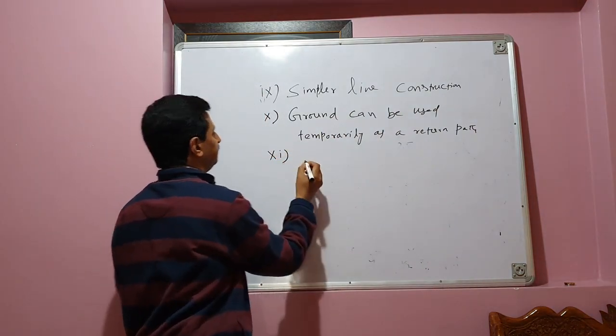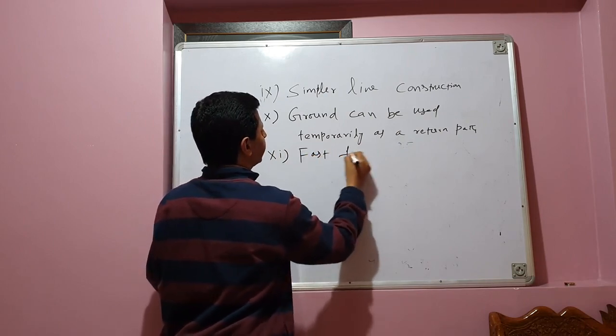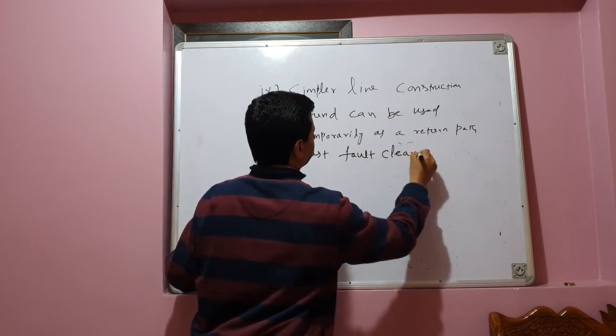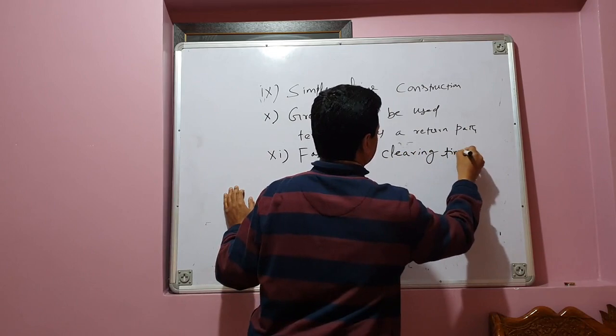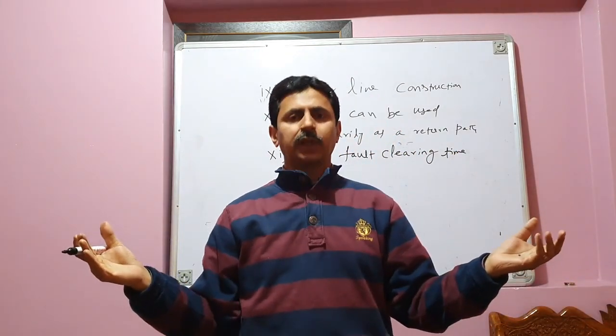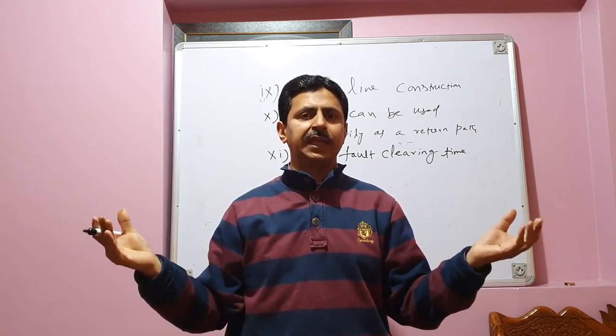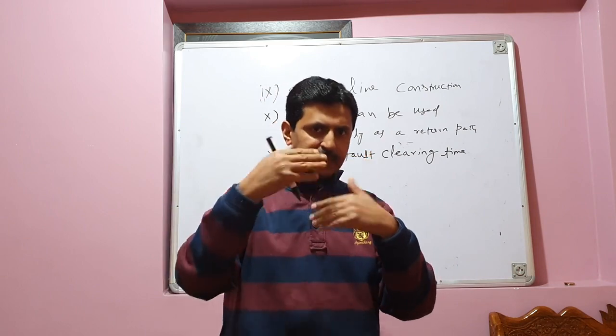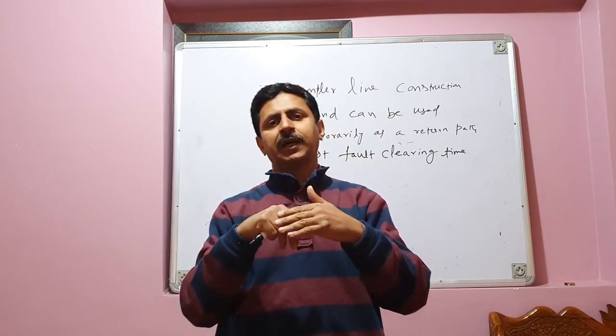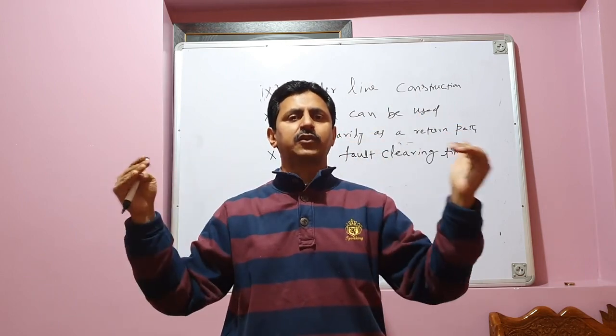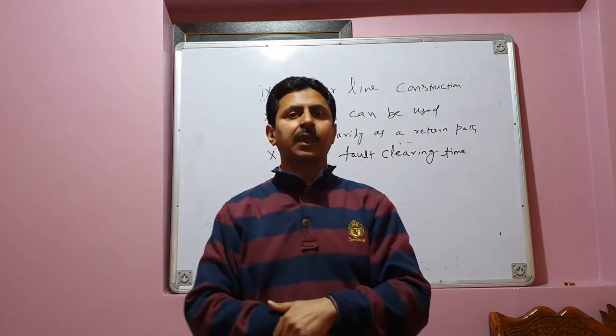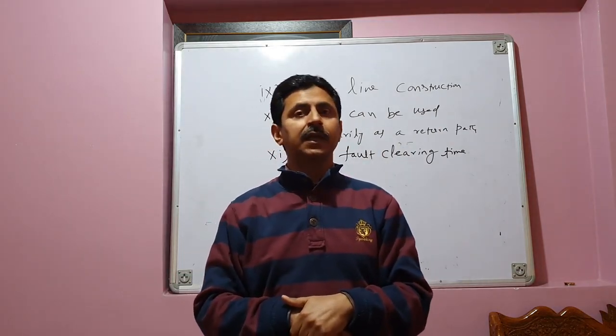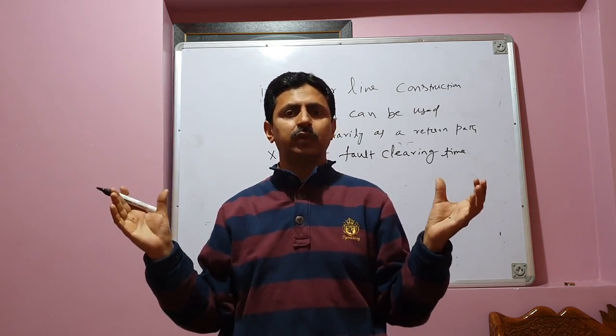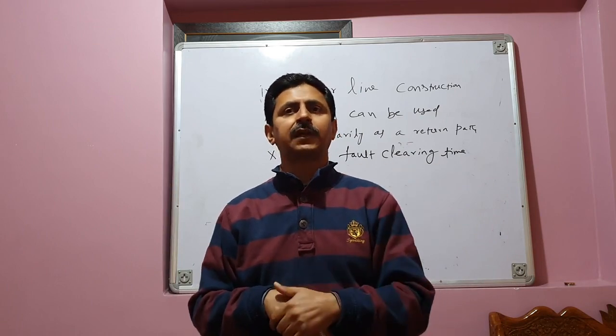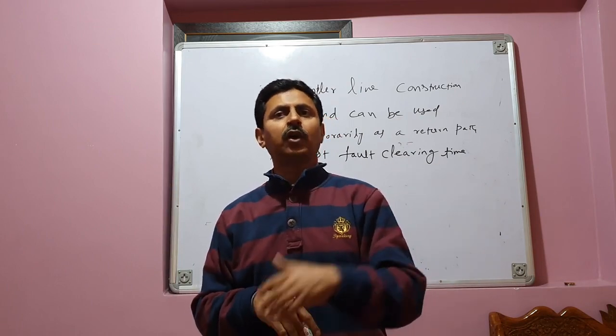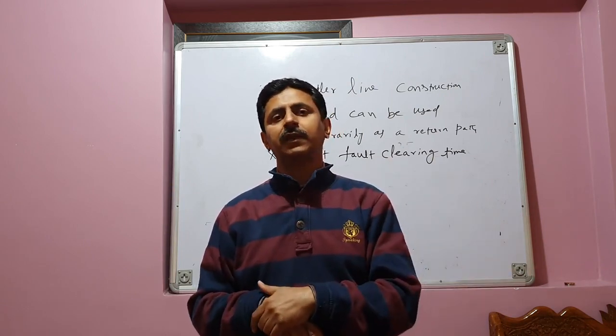Next is fast fault clearing. Fast fault clearing time. If a fault occurs on an AC transmission system, what are the devices which clear the fault? Protective devices like protective relays, circuit breakers. It takes time for a protective device like a relay to sense the abnormal current and then give a signal to the circuit breaker, and the circuit breaker then trips and disconnects the faulty line from the healthy system. Whereas in HVDC power transmission system, we don't have any circuit breakers. It is completely electronic control. We are using thyristor converters, and these converters are electronically controlled, not electromechanically. So the fault clearance is very, very fast. Okay, another advantage.